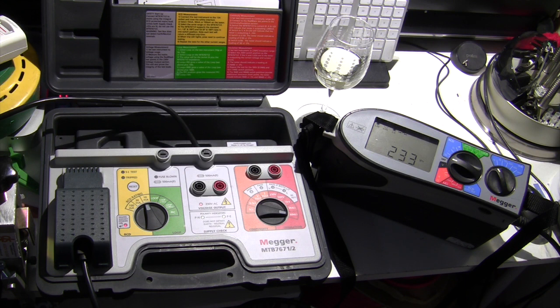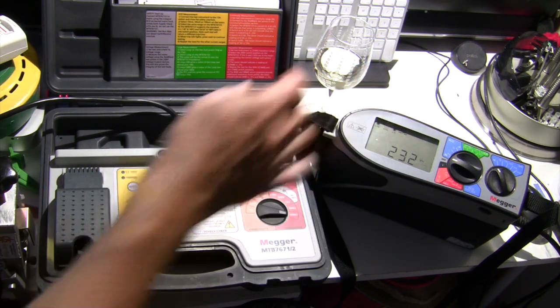Now this particular tester, the 1552, will perform that test for nearly 2 seconds before it comes back with a pass, assuming that there hasn't been a trip within that time. The regulations, I believe, state it's got to be able to take that for 300 milliseconds, if I remember rightly. And the Fluke will test for 310 milliseconds, but the Megger here does go for nearly 2 seconds. So we're going to press the test button, and like I say, if the test is successful, this shouldn't trip, and that should show that we've got a duration of over 1999 milliseconds. So that was a successful test. And that's the half times test done.